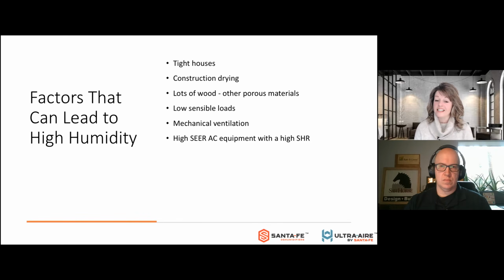Our AC equipment is becoming extremely energy efficient. And when we say it's energy efficient, that means it's energy efficient at getting to that sensible temperature, not necessarily energy efficient at removing water. And that's what the high sensible heat ratios are. We don't have a lot of dehumidification capacity with our really energy efficient AC equipment.